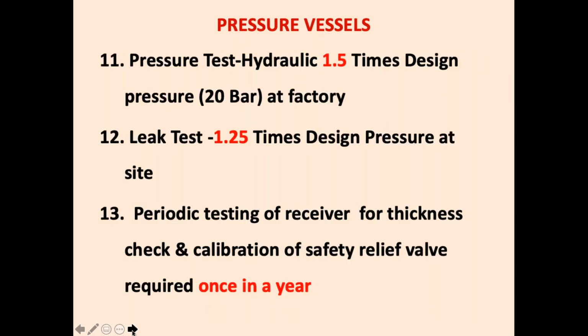The pressure vessels should be hydraulically tested in the factory at 1.5 times the design pressure, and at 1.25 times design pressure for the leak test at site, with periodic thickness testing of the receiver and checking calibration of safety valves once in a year. The thickness can be checked externally, not by removing the ammonia. There are thickness sensors now available, and they will show you where the thicknesses have gone down below the design values. In that case, you have to replace the vessel with a new one.